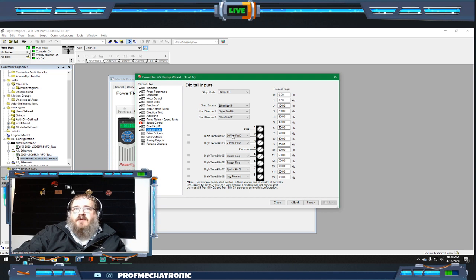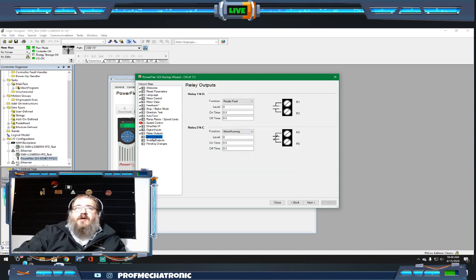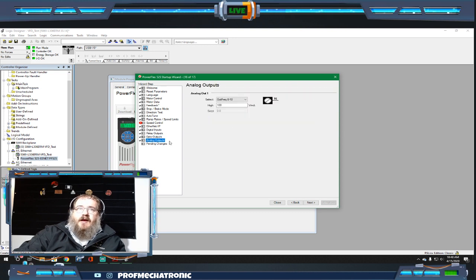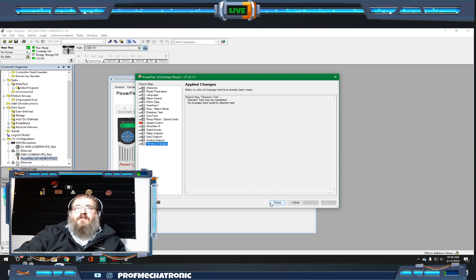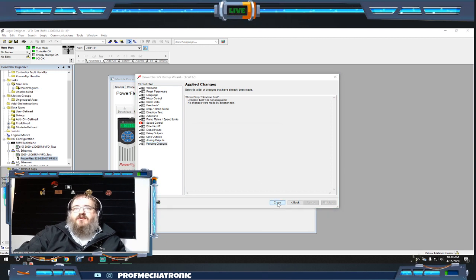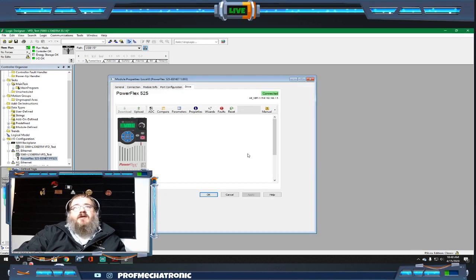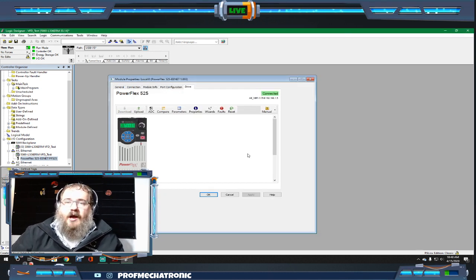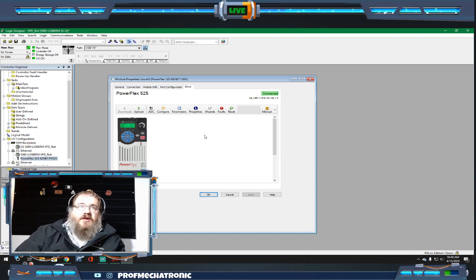Digital inputs, how do you want those wired if you're using them? Relay outputs, optical outputs, analog outputs, and then it asks if you want to actually download those to the PLC. We didn't do any of those things, so we'll close this off since we don't want to download any of those parameters. But the wizard is extremely helpful for setting that up, and that's one of the advantages of having this configured over Ethernet IP — we can have access to all of this information.